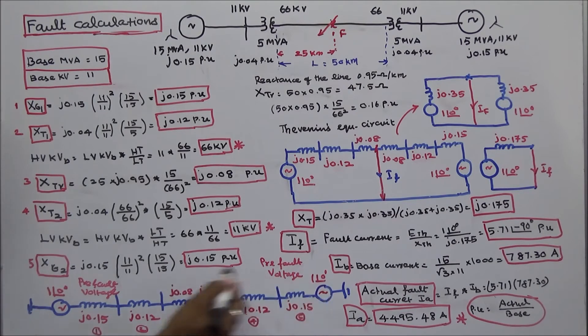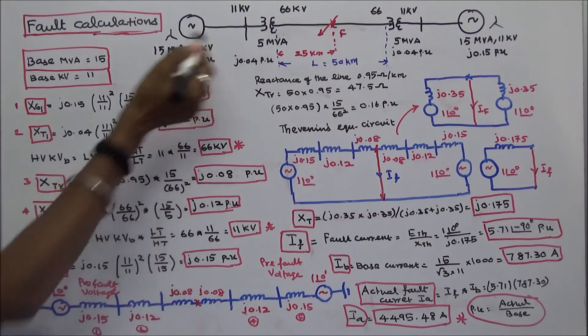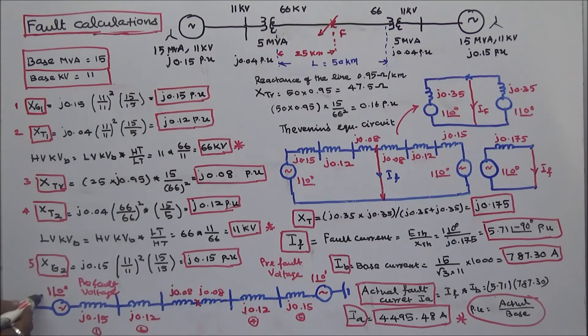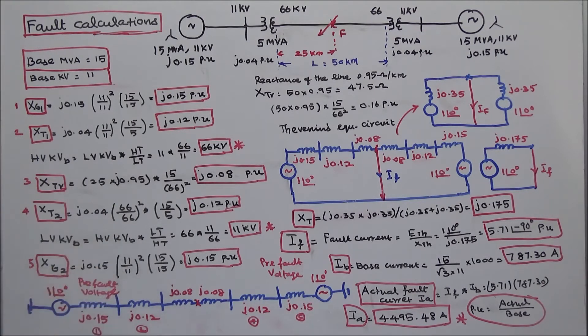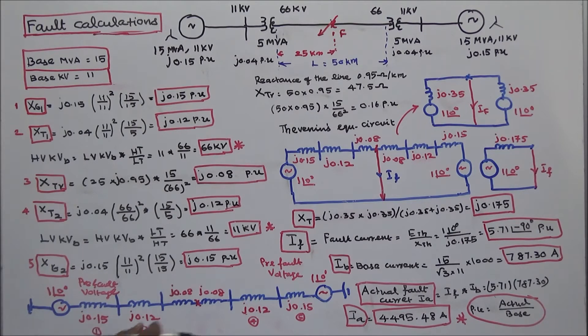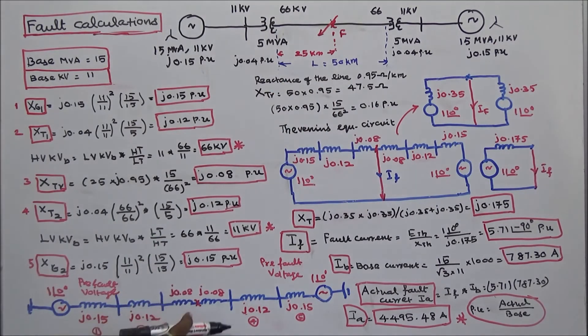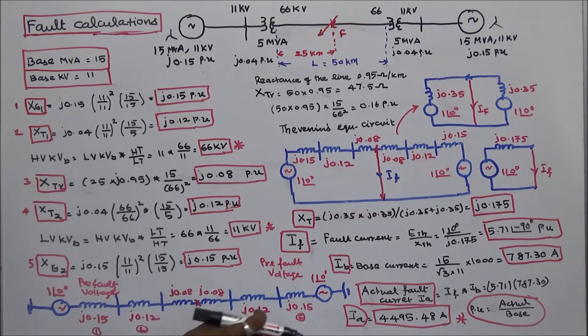The second step is to draw the reactance diagram. The pre-fault voltage is 1∠0°. The reactance of Generator 1 is J.15, Transformer 1 is J.12, the transmission line for 25 km is J.08 on each side of the fault point, Transformer 2 is J.12, and Generator 2 is J.15.